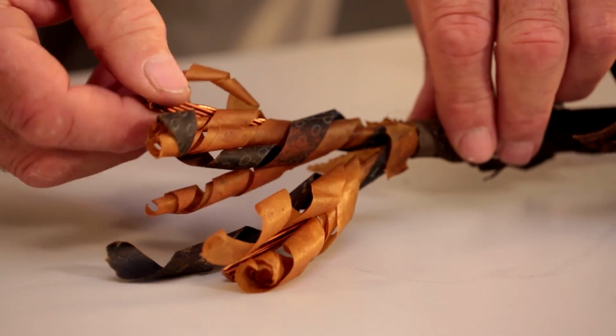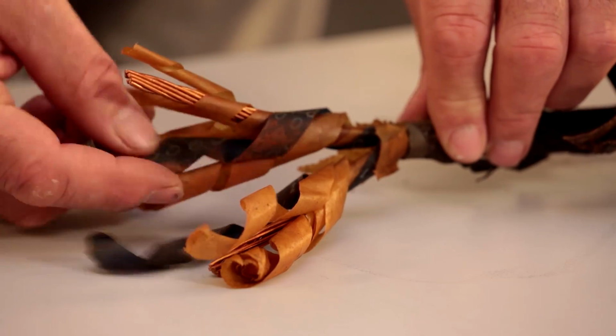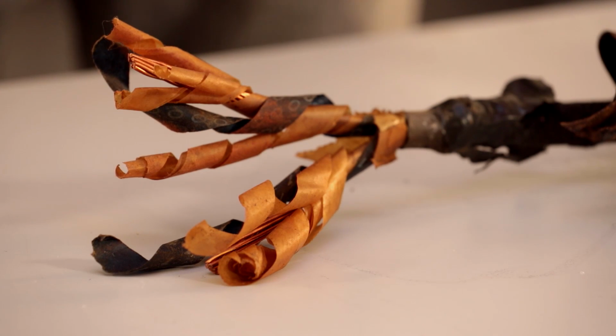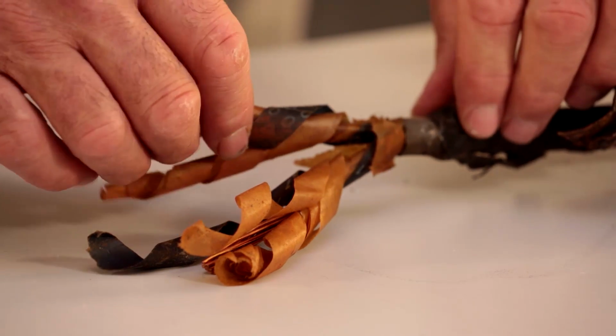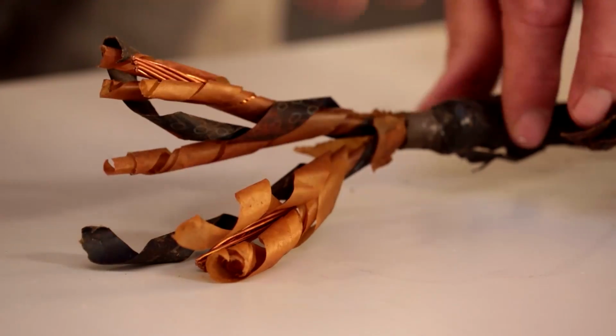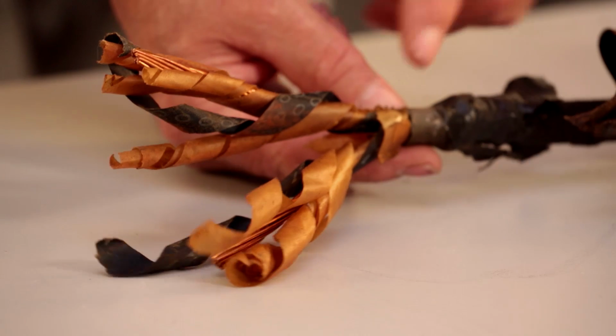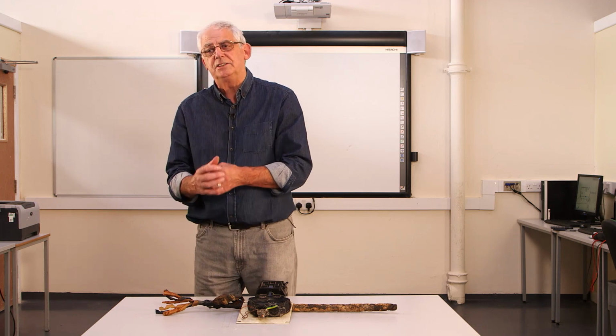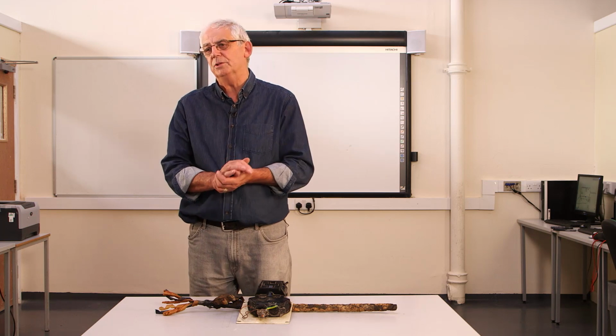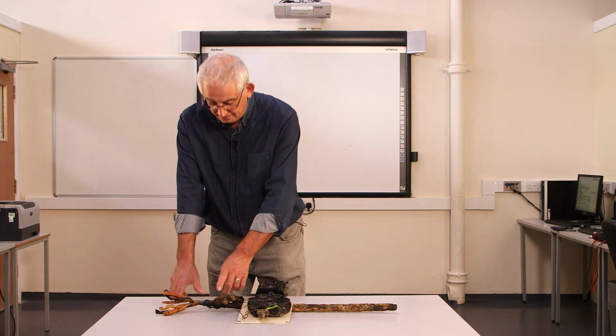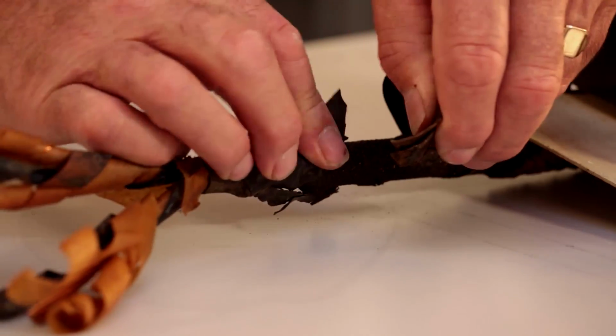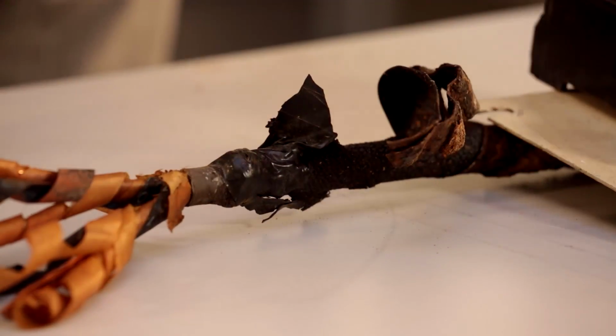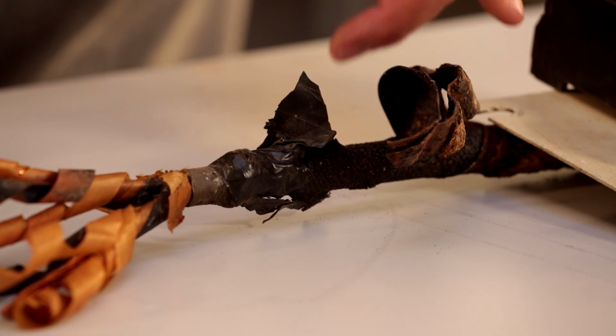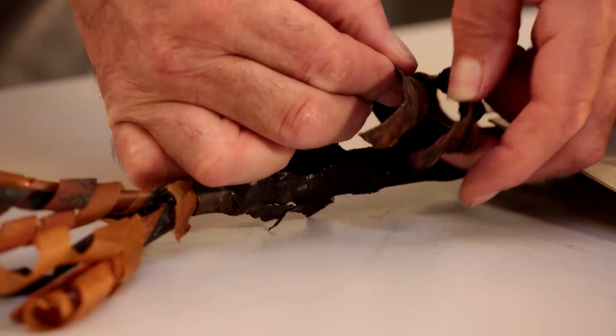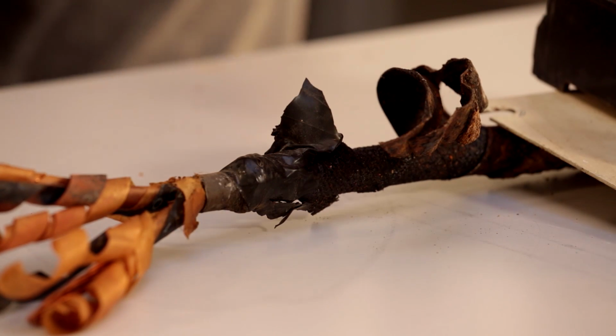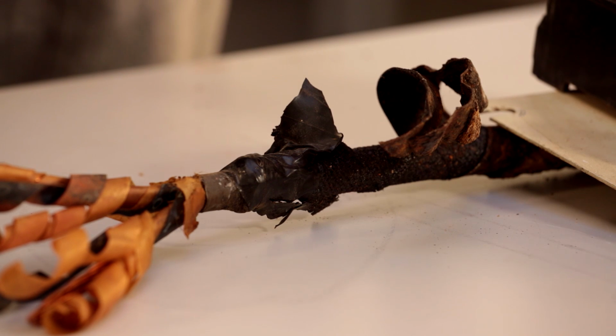The cable would be copper conductors insulated by oil-soaked paper, and then after that it has got a wrapping of paper around both conductors, and then it's covered by a lead sheath. The lead sheath would run continuous throughout the whole of the cable. Then it's wrapped with hessian, as you can see here, around the outside of the lead, and around the outside of the hessian there's strips of flat steel, which gives it a very, very good armoured protection.